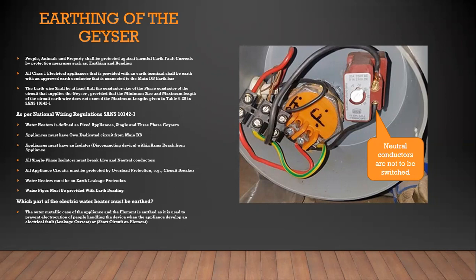We've also addressed what must be bonded, how to bond it. All water heaters must be on earth leakage protection. That's a regulation. A simple check to do, you can test up in the geyser: you can trip the client's earth leakage in the DB board by pushing the test button, and then check if the geyser still has power or not. If it has power, you need to inform the client, so your water heater is not wired according to regulation. Please get an accredited electrician out. So this is all basic general knowledge for you as a plumbing professional to gain that knowledge and to enhance your business.